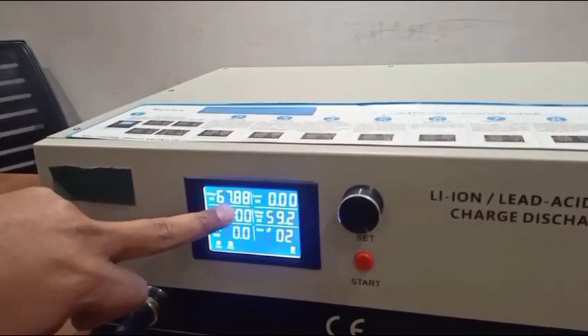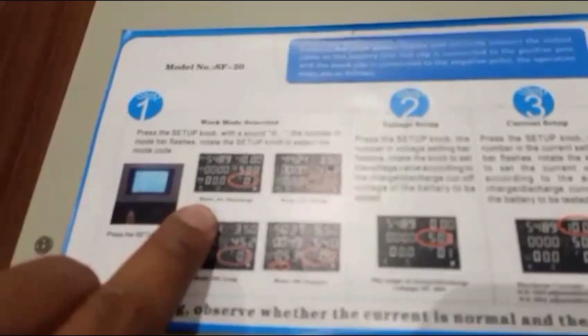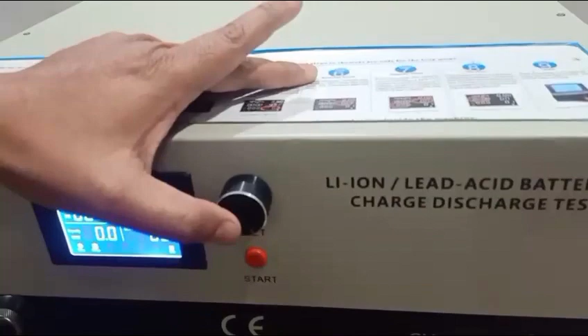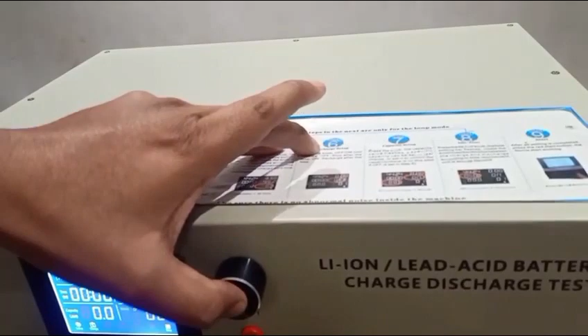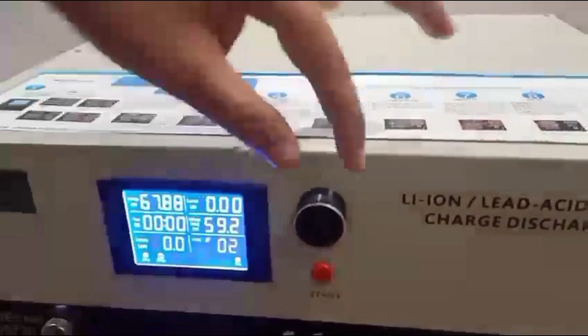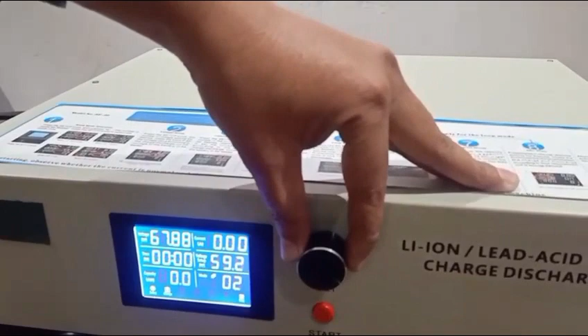For discharging you will need to go to mode number 1. First select the mode by pressing this button. After pressing, you can see this one is highlighted here, this is the mode. If you turn this knob right or left, it will change the mode of this machine. Since I want to discharge this battery pack, I will use mode number 1. After putting 01 here, simply press this knob, and now you will have to tell which voltage you want to discharge this battery pack to.